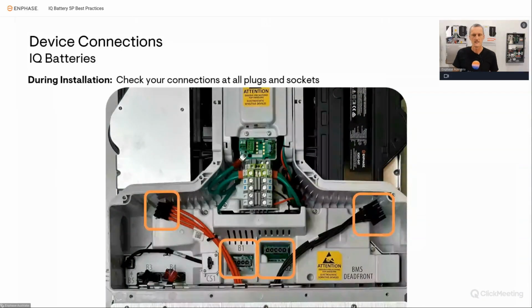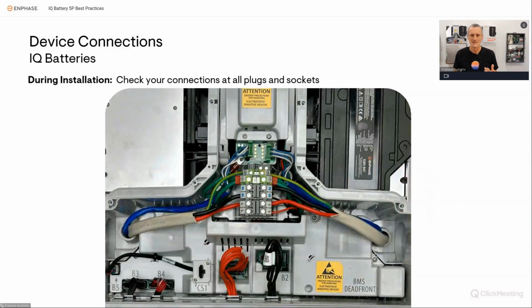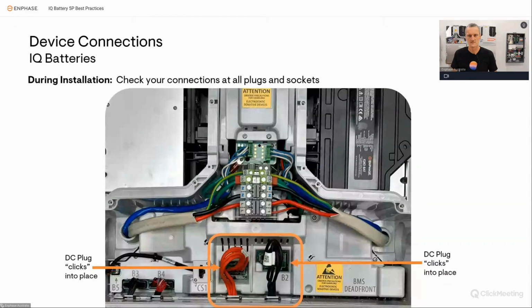There's a connection lead for the positive conductor for the battery, and also a negative conductor lead for the DC battery connection. Those sockets are B1 and B2, which should be fairly easy to remember. That's something we picked up in the field — we found that some of the seating may not have been completed correctly, so please look out for that during installations, and listen for that click as it goes into place.